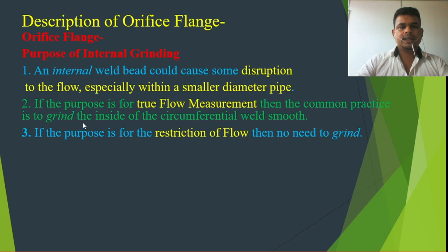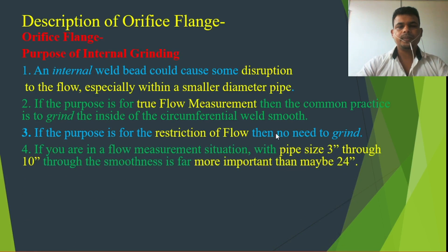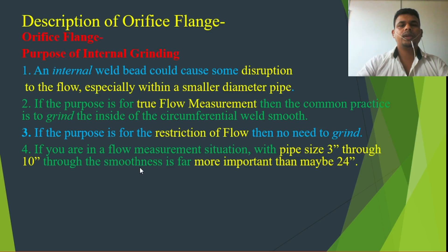If the orifice flange is used for restriction of flow, then there is no need to grind. Also, if you are in a flow measurement situation with pipe sizes 3 inches through 10 inches, the smoothness is far more important than for maybe 24-inch pipe. So for smaller pipe sizes it is more important to grind compared to bigger pipe sizes.